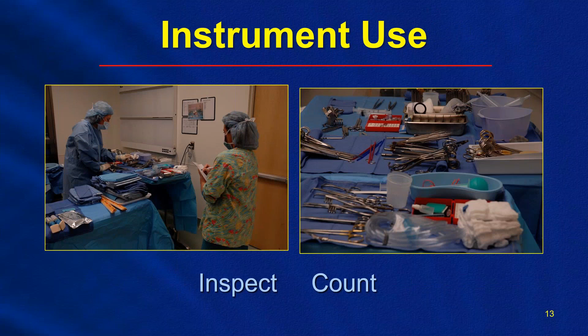So preoperatively, when setting up for a case, the RN scrub or the surgical technician will first look for and check the indicator in the tray, which would show that the instruments have been subject to the proper sterilization method. Further inspection would look for any irregularities on the instruments, such as staining, any rust or corrosion, pitting, damage, or foreign materials. Sometimes foreign materials inside the tray. We've opened trays and seen pens and other things that don't belong in there. Then an instrument count will be performed with the circulator and the scrub to make sure not only that all of the instruments are there, but that they are the correct instruments. Also checking the instruments for proper functionality should be done by the scrub person.